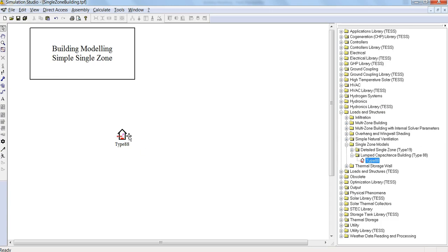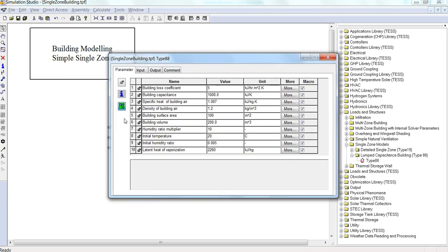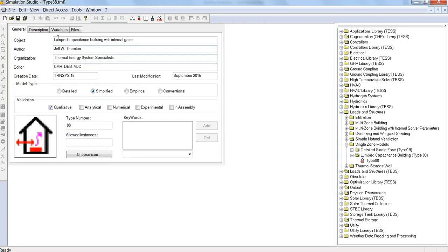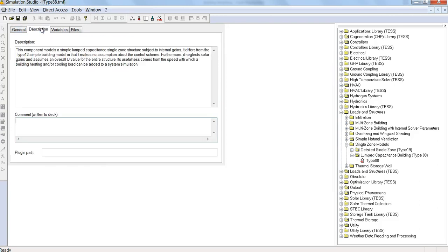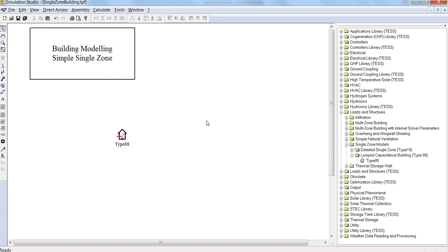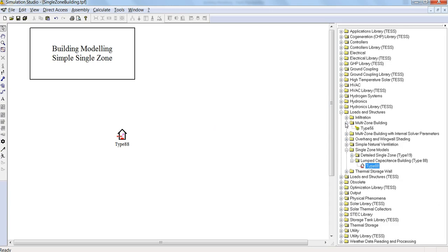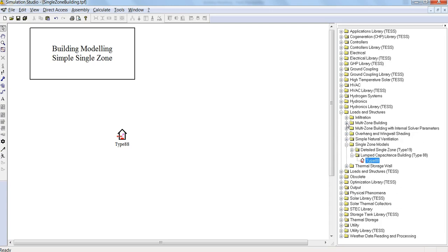So what this is, is just a simple lumped capacitance building model. It's very simplistic. We have some internal gains, there's no solar gains, and we just assume an overall U value for the entire structure. So this is just a good model to think about how building modeling works, and later on we'll move on to the more complex multi-zone building model, type 56.